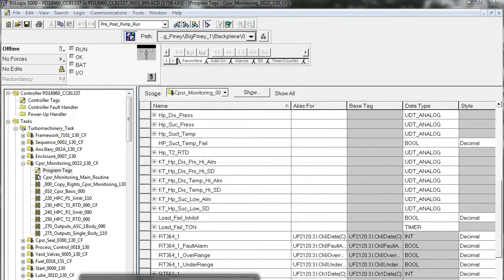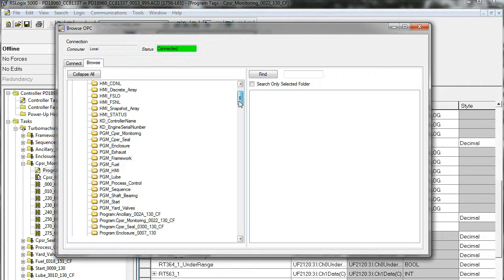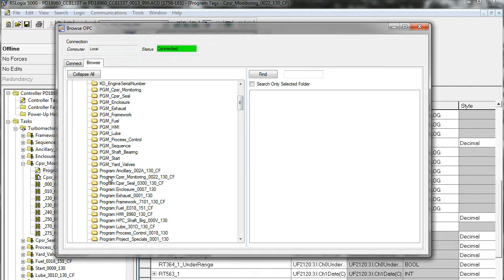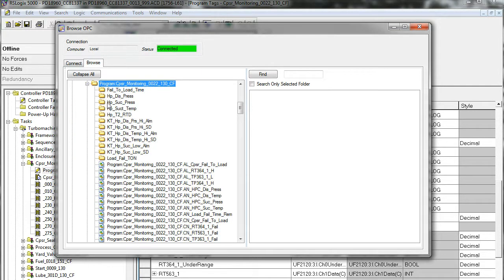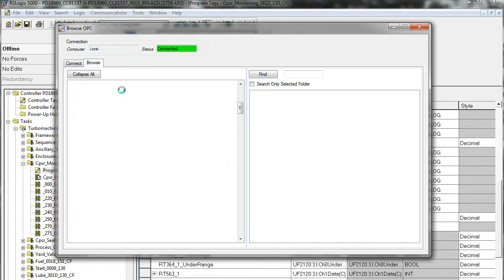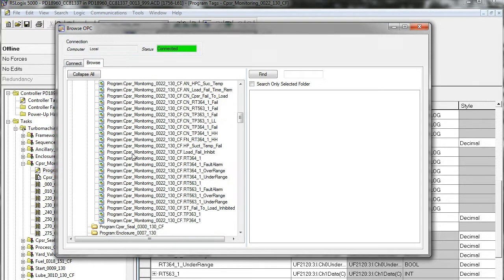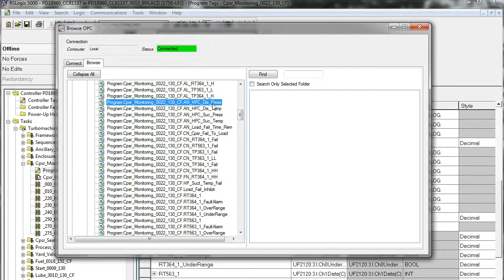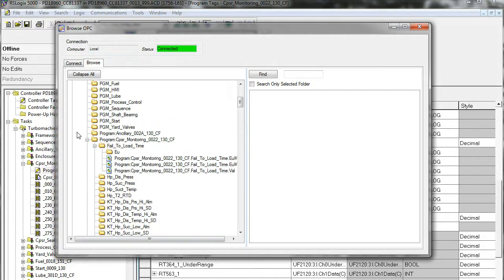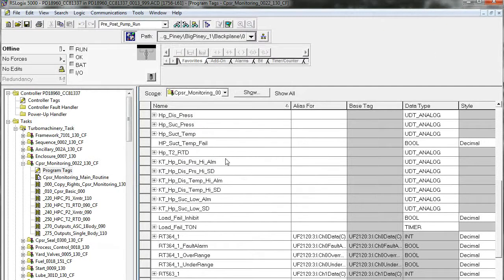Now let's browse those through StripChart OPC. It's hard to tell what's program scope versus controller scope, but if you look closely you'll see 'Program:' and then the name of the task. Here, 'compressor monitoring' is the one we were looking at in the ACD file. Opening that up, we find all these elements — some are more complex variables with sub-variables underneath a structure, while others are directly accessible through the program scope. For example, this analog appears to be discharge pressure. That's a little overview of how the data structure when browsing in StripChart OPC correlates to the data structure in a ControlLogix file.